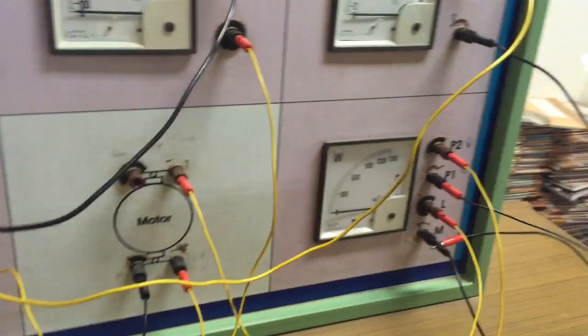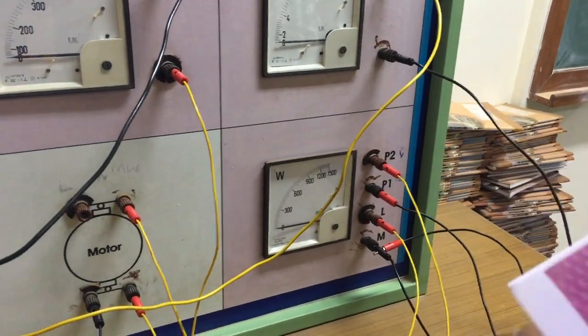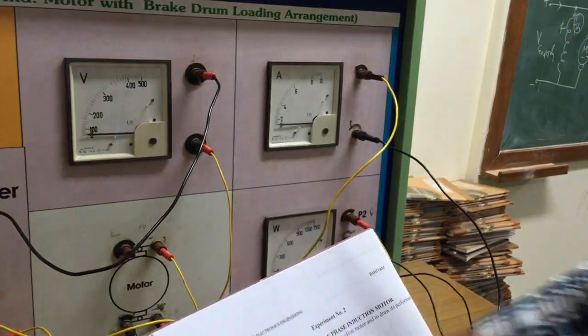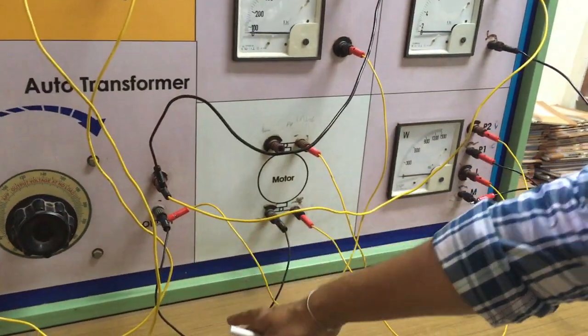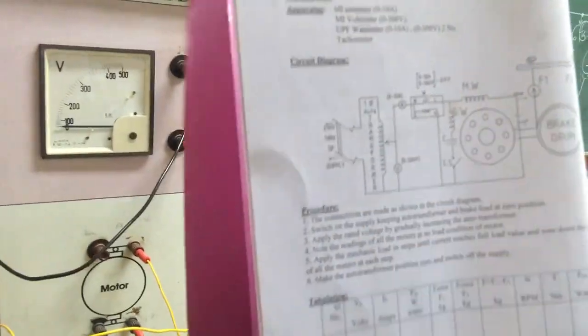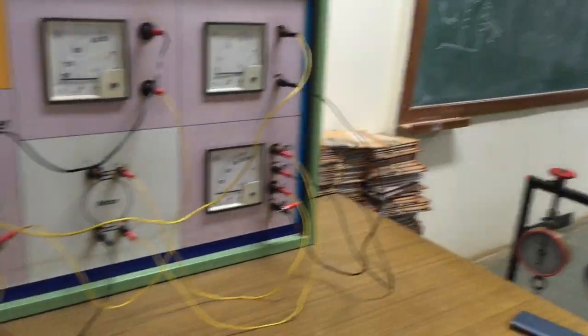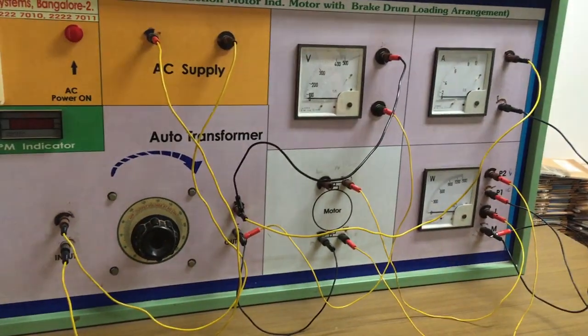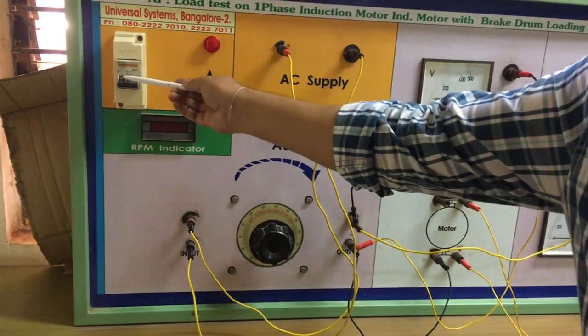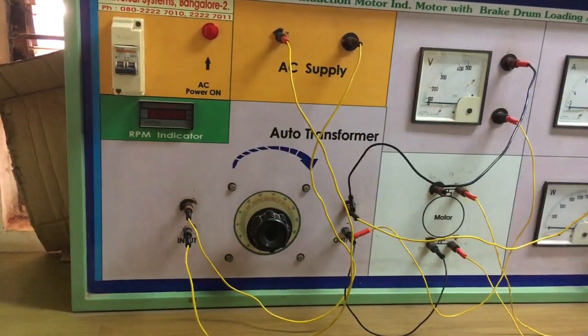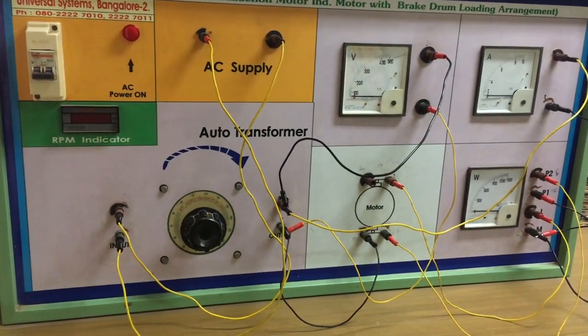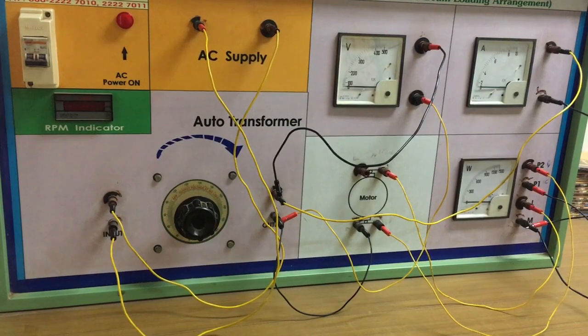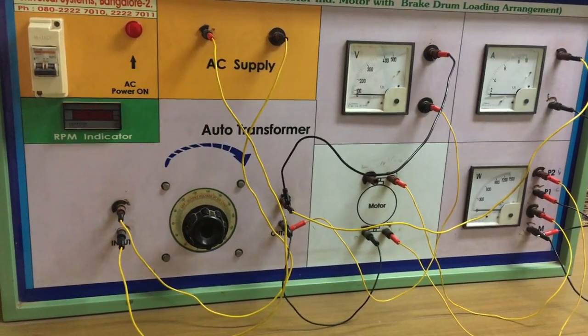Then the mains and common are short circuited. This M and C is short circuited, whereas V is connected to the neutral of the motor, and the neutral of the motor is connected to the neutral of the supply. So this forms the circuit connection for the load test on the single phase induction motor. Here I have the supply switch MCB, and this is the RPM indicator. The digital speedometer is mounted on the panel, so I need not go to the rotor and check the speed. Directly the speed is available on the panel itself.